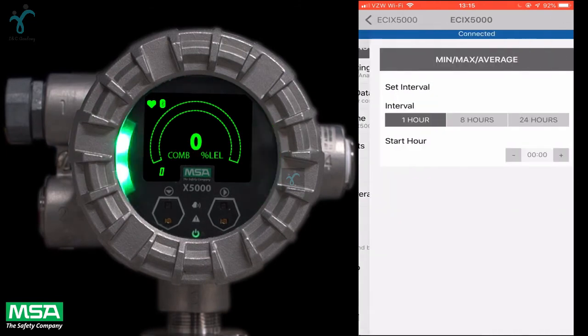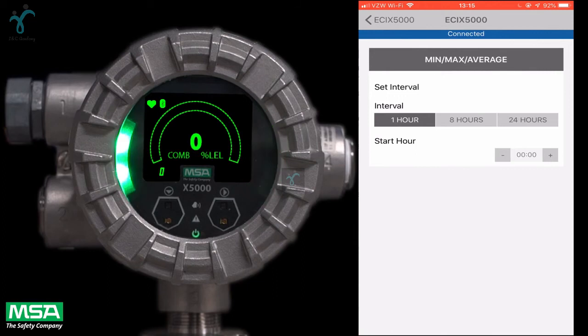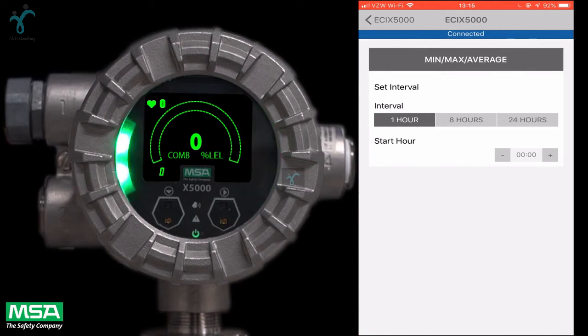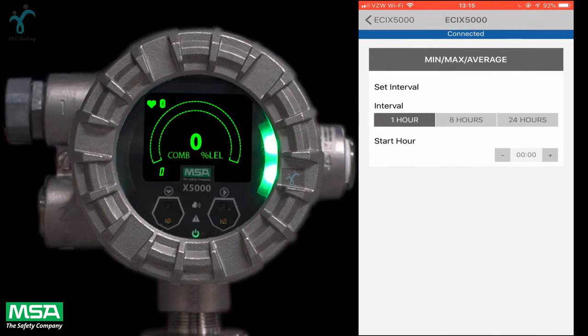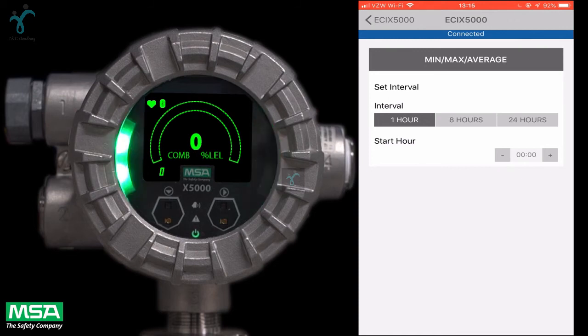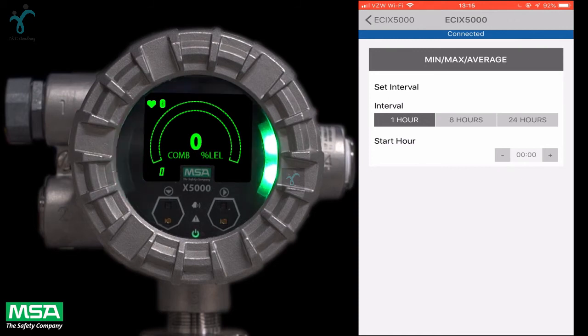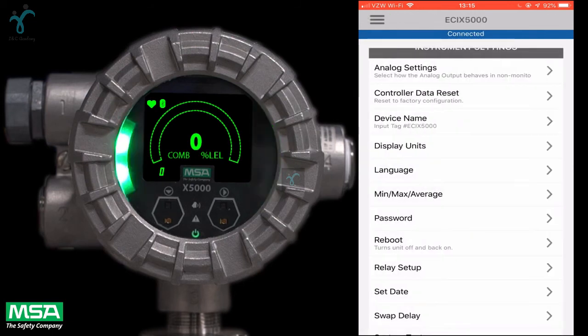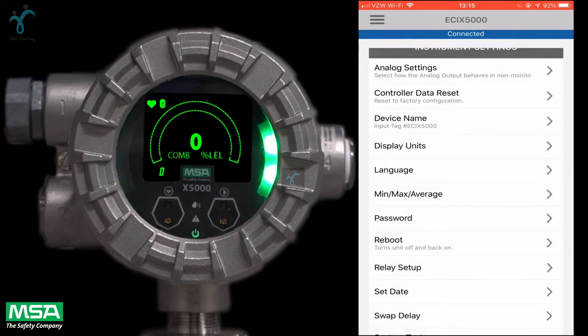The min-max average can be set up for a user-defined interval. For example, if the interval is set to 24 and the start hour is set to 6, the min-max average value will update every 24 hours at 6 a.m. These values are driven by the date and time of the transmitter.